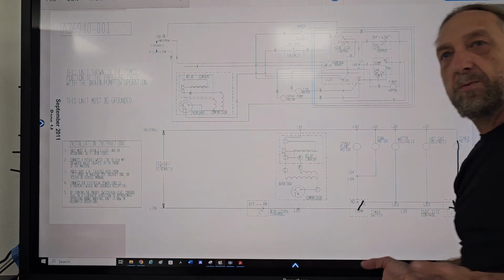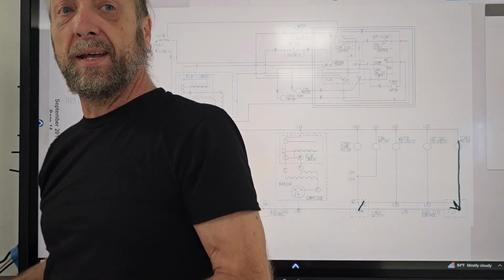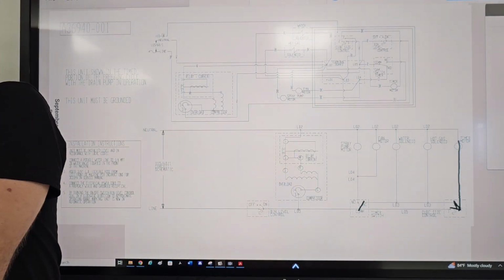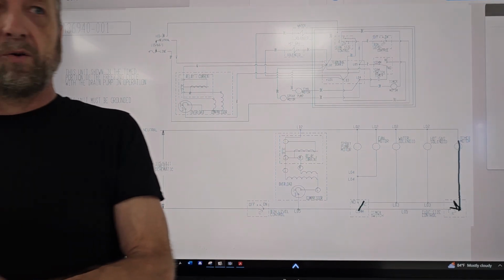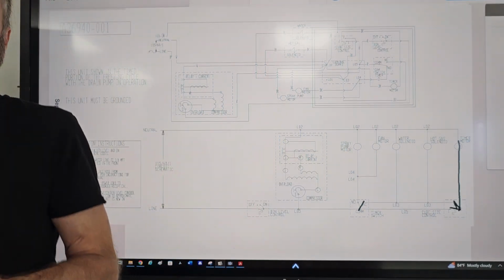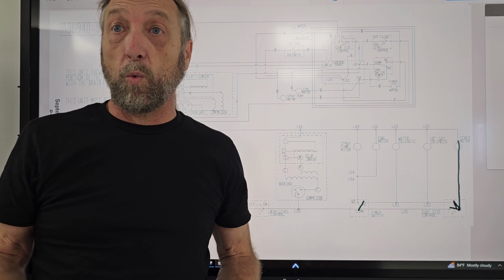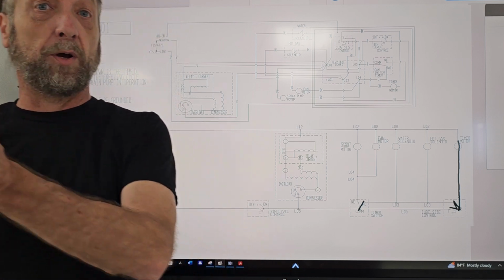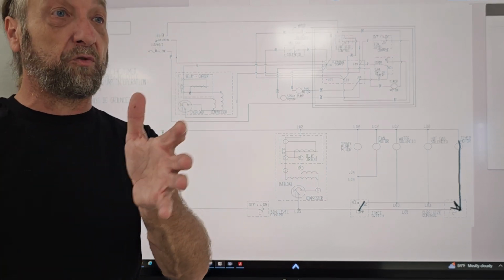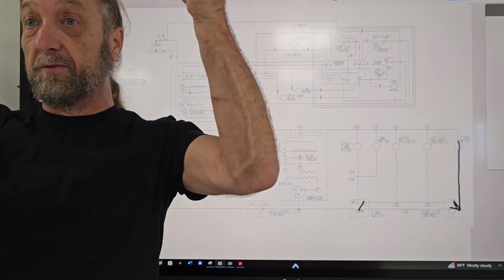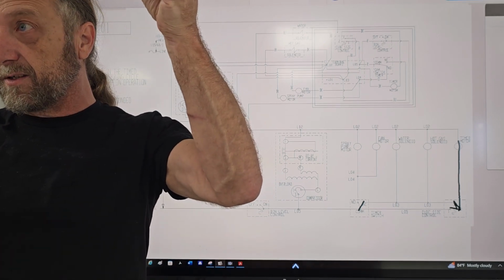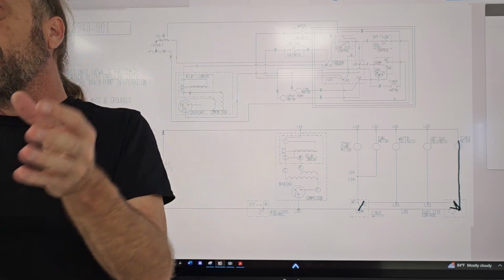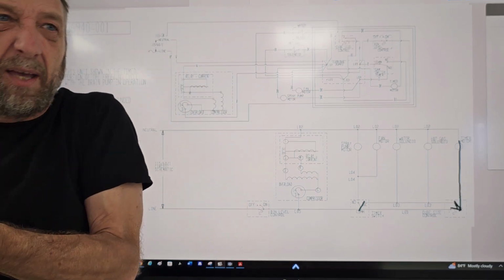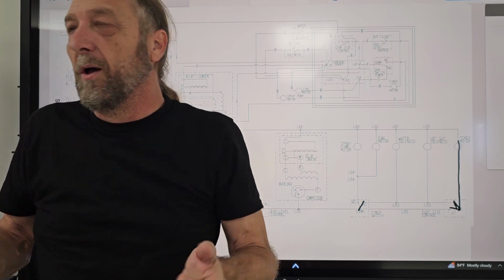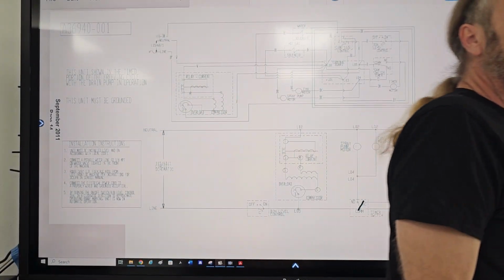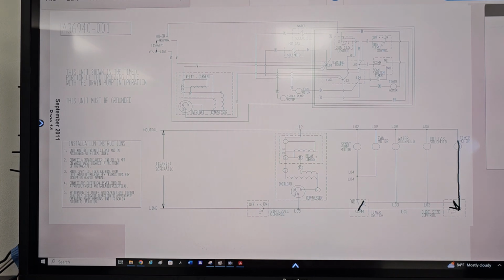On average, these ice machines take 20 to 30 minutes to produce ice. And they were running it the other day and said, oh, I need to close the door. No, you can run an ice machine with the door open and watch it. Again, it's not a refrigerator or freezer where the air in the box freezes the ice. It's the actual evaporator. When the water touches it, it makes the ice. So it doesn't matter if the door's open or not. Will it affect it a little bit? Maybe a little, maybe half a minute or so. But the timer will run for about 20, 25 minutes. I don't know the exact time. I'll have to look at the manual.